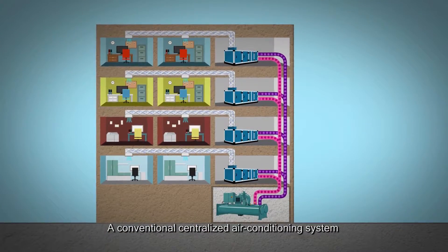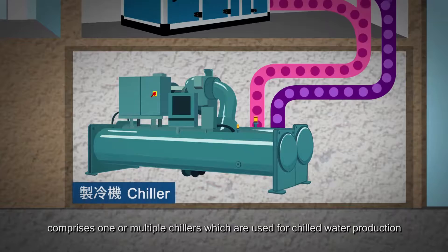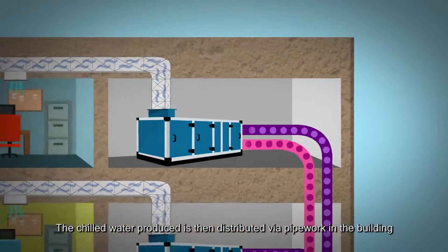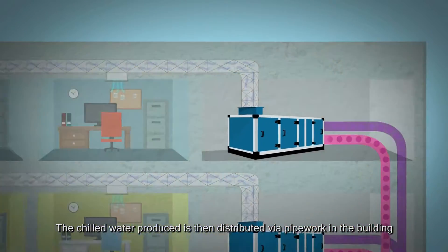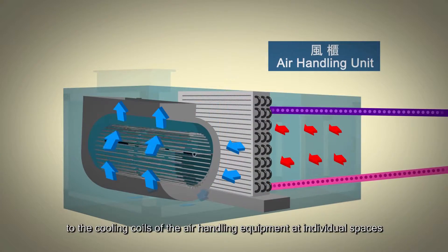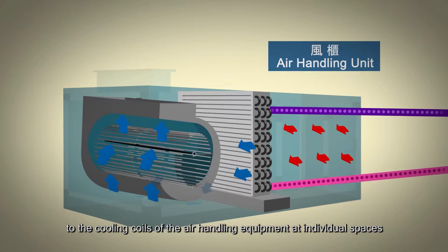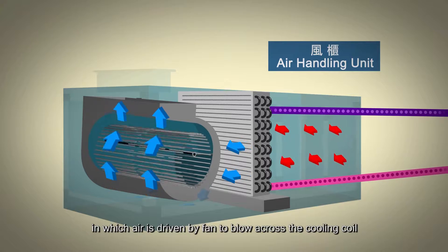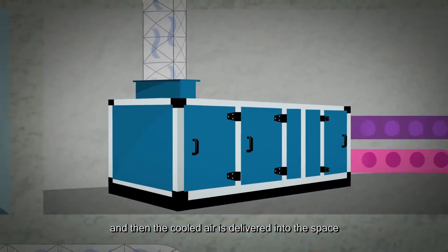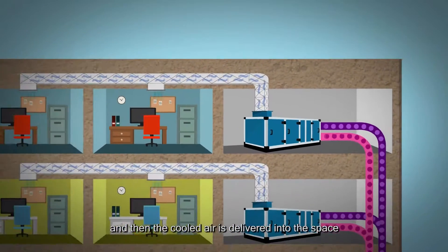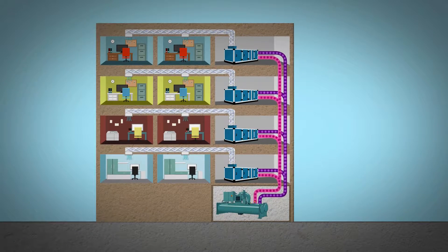A conventional centralized air conditioning system comprises one or multiple chillers, which are used for chilled water production. The chilled water produced is then distributed via pipework in the building to the cooling coils of the air handling equipment at individual spaces, in which air is driven by a fan to blow across the cooling coil, and then the cooled air is delivered into the space to achieve overall air conditioning for the building.